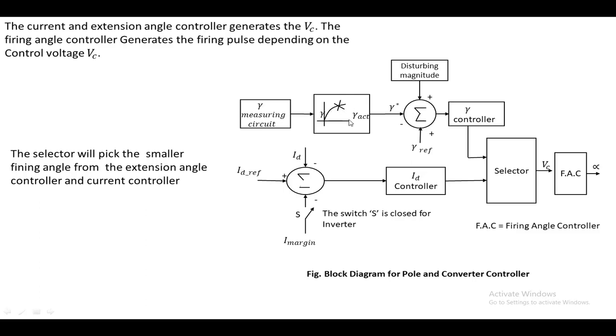When the measured gamma is passed to the delay circuit — suppose gamma is 15 degrees — the gamma angle does not suddenly change from 0 to 15 degrees. When fed to the delay circuit, the gamma angle slowly ramps from 0 to 15 degrees, and that value is taken as the reference. Any disturbance is also added to this, giving the gamma reference. From the gamma reference and the measured gamma, the difference is taken and given to the gamma controller. The output of the gamma controller is given to a selector. The other input to the selector comes from the current control loop: the difference between the ID reference and the actual DC link current is given to the ID controller, and its output is also given to the selector. The selector selects the lower firing angle value depending on the gamma control and the current control.